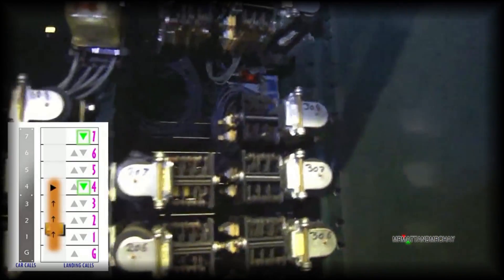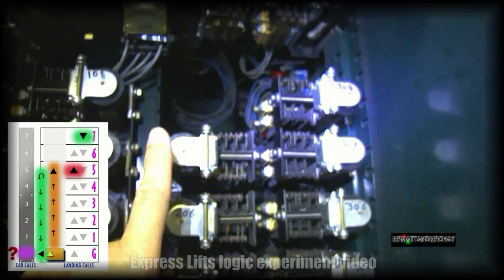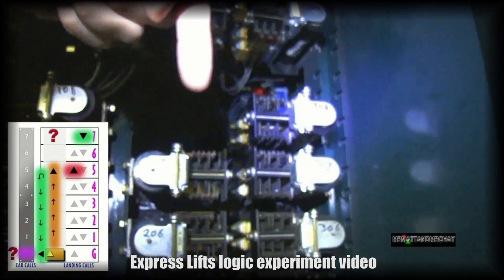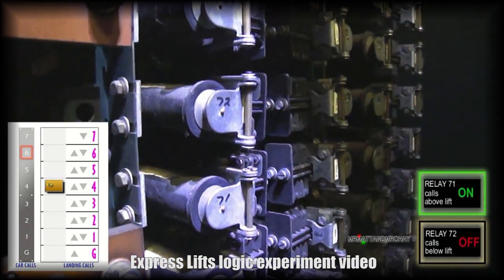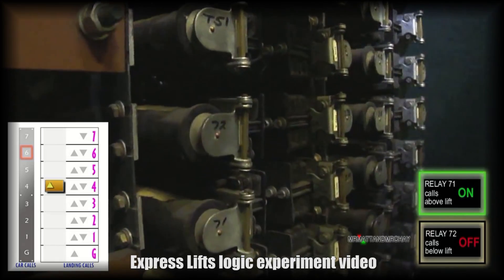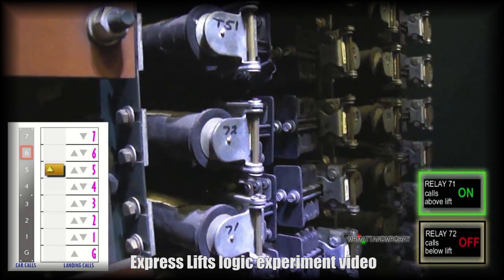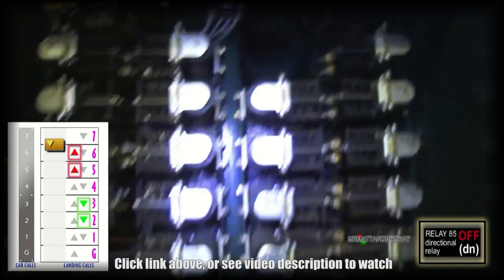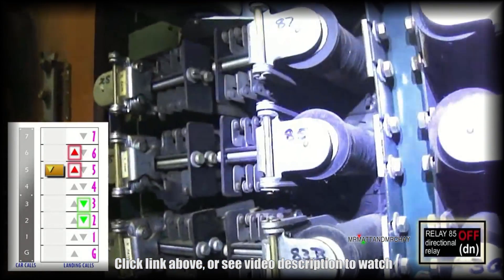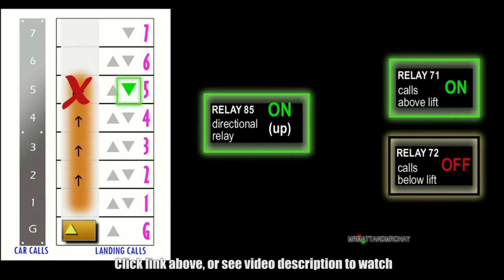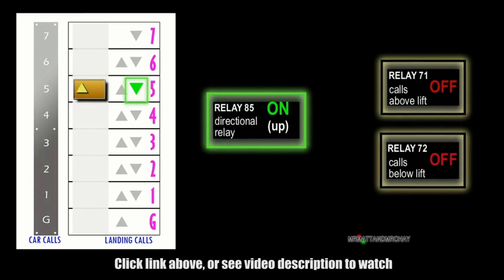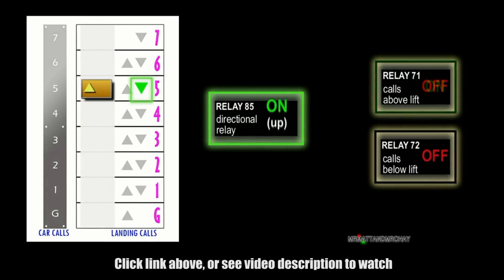I have many videos explaining old lift logic, including this one where I perform loads of relay logic experiments. Will it continue up to get the top floor and then come back down? Give it a call. First floor. Yep. Give it a couple of up calls. That one and that one. Directional relay. It's pretty basic relay logic. No destinations, just keep going until the relevant relay turns off.